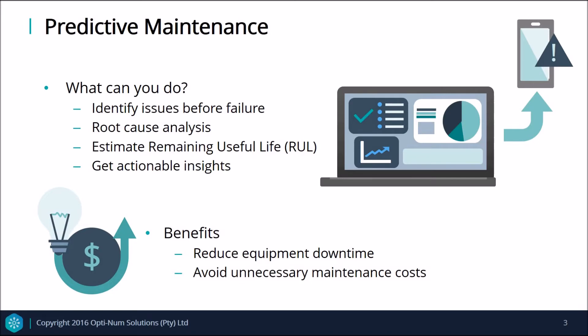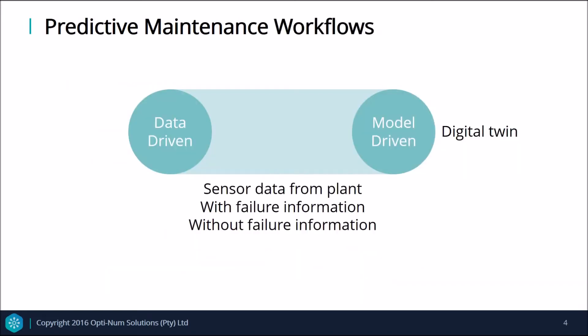So how do we go about implementing predictive maintenance? Based on the data that we have available, we can decide on an appropriate workflow. In general, the workflow can be data-driven or model-driven. With a data-driven workflow, we only use the sensor data from the plant or equipment to create a predictive algorithm, which will differ slightly depending on whether failure information is available or not. When we don't have failure data, we may decide to simulate failure information by creating a digital model of the physical plant and then test multiple scenarios in a safe, low-risk digital environment.